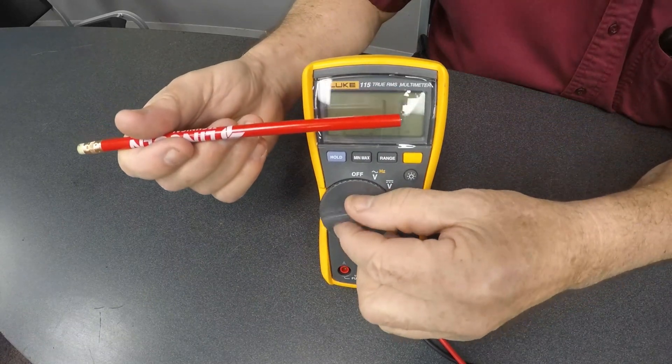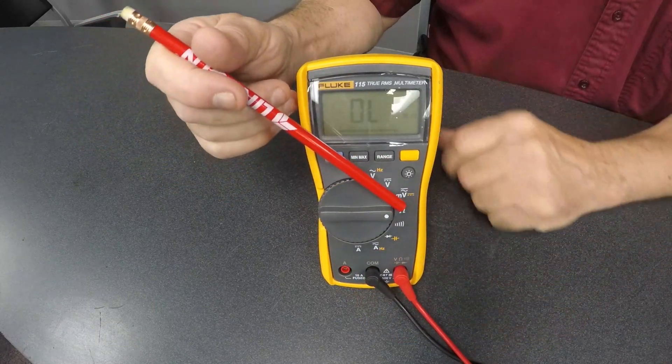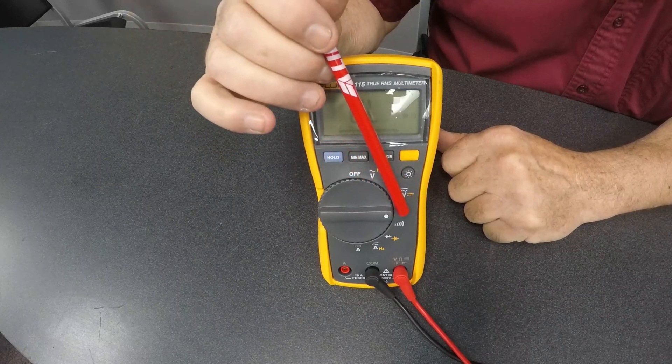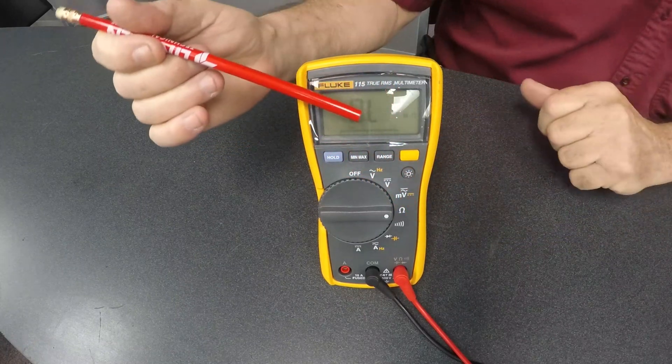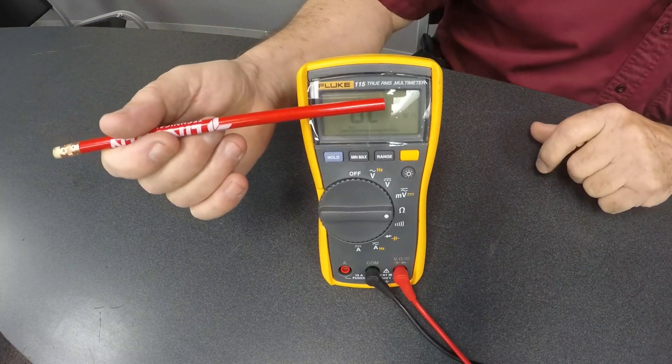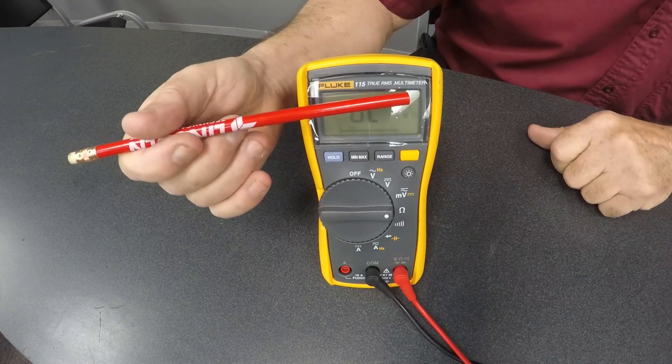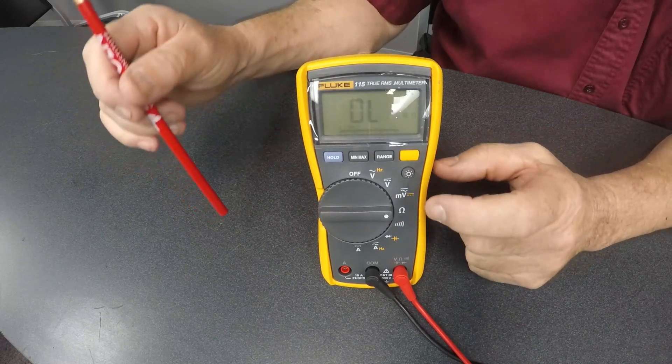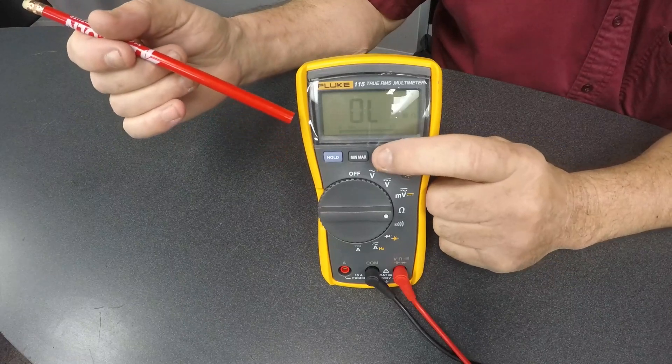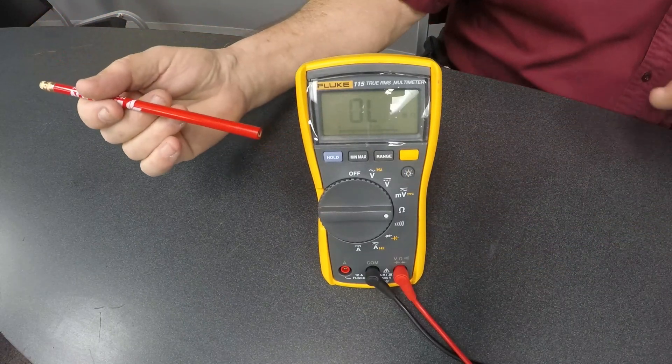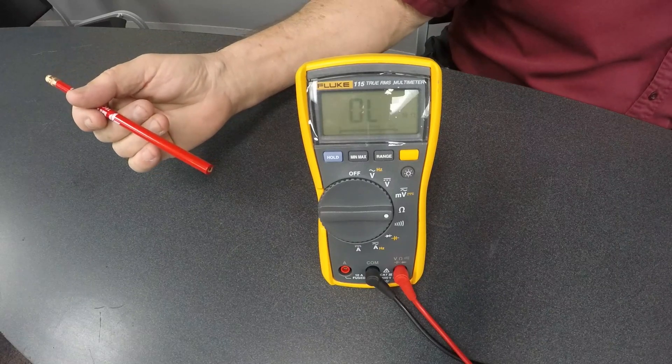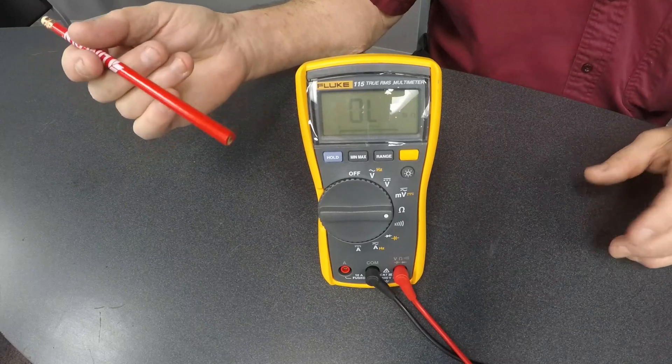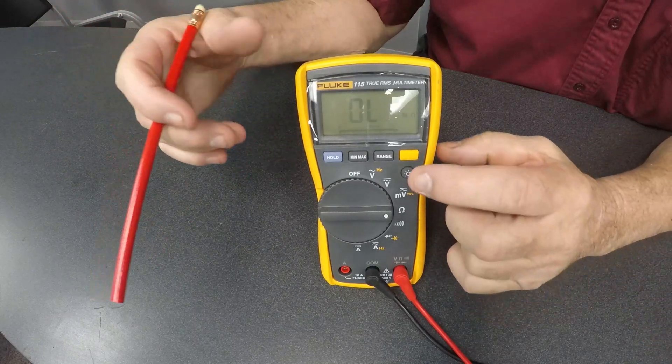Next one is down here. It looks like the horseshoe. It's the omega sign for ohms. Ohms meaning resistance. We have it, you can see when you set it to ohms, it's auto-ranging, so the first thing it does, you've got that capital M over here in the corner, and that stands for mega-ohms. If we were to hit the button again, the range button, you can see it still says mega-ohms, but now on the bottom here, it says manual. It's no longer an auto-ranging meter. You're doing the thinking for it. It's not thinking for you.